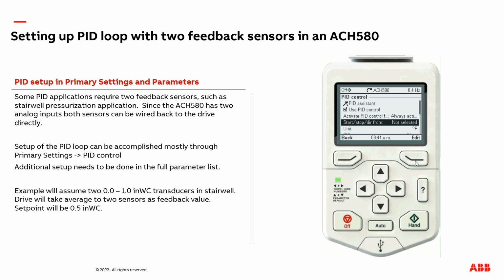We now need to select where the run stop command comes from when we're in auto mode running the PID loop. Most likely, your selection will be the same as mine, which is digital input 1. We next need to adjust the units. We're not degrees Fahrenheit, we're doing inches of water column. Now, we need to make an adjustment for one of the analog inputs, which is one of our feedback sources. In here, we're going to adjust AI2.